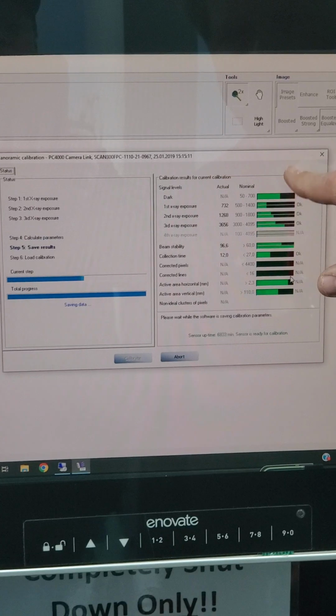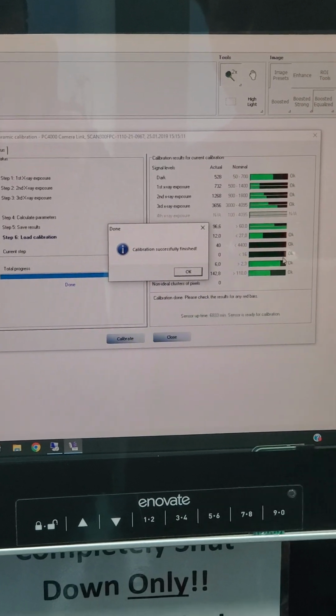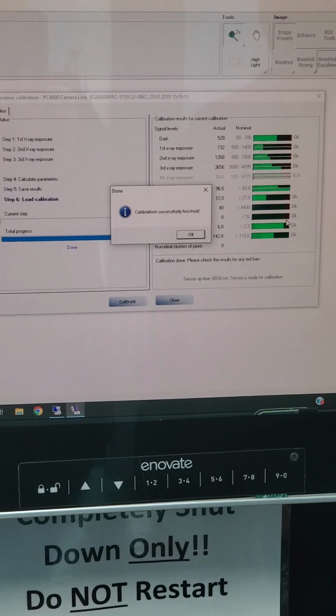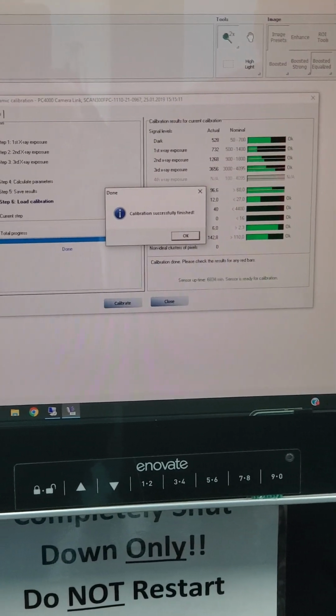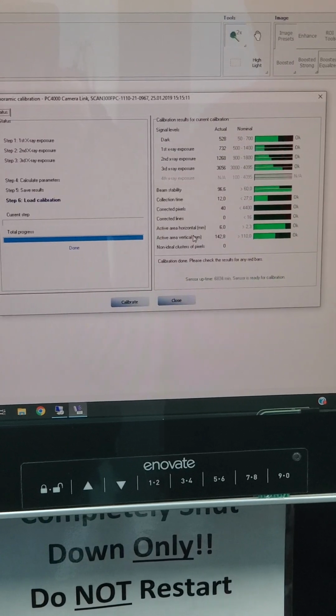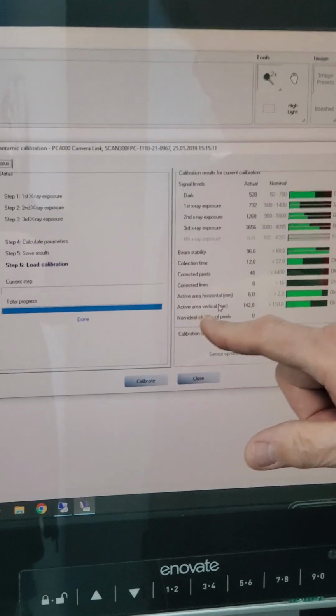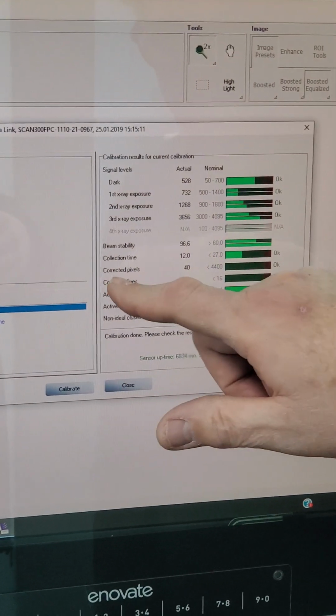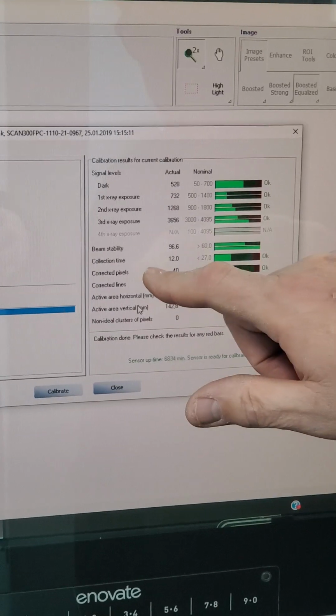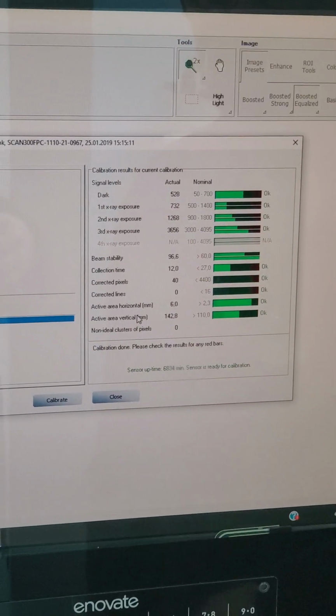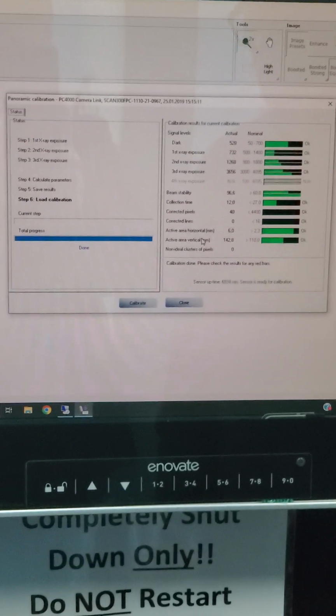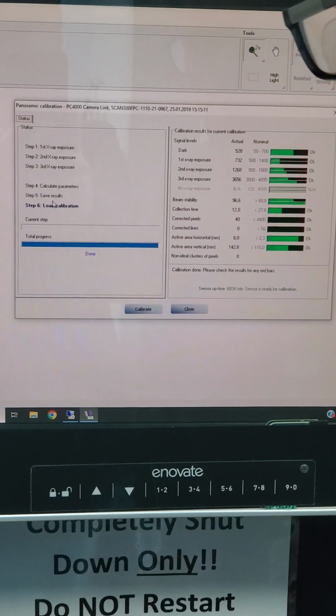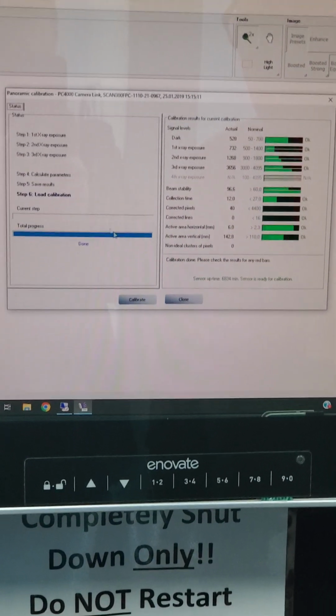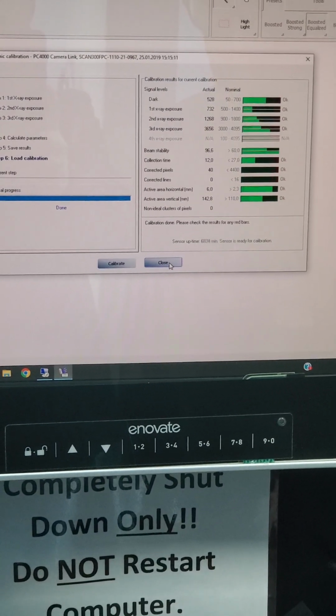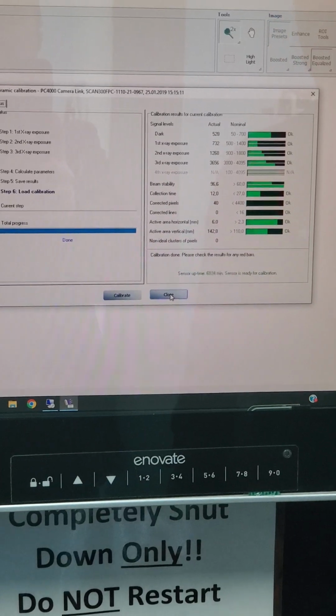So what we're looking for is all of our sliders in the green, and they all are. And we have a successful calibration. Yay! So we're gonna click OK here. We're also going to observe our non-ideal clusters, 0, excellent. Corrected lines, 0, excellent. And only 40 corrected pixels of all of those pixels of that sensor. So the sensor is in A1 condition. It's in great shape. All right, so everything's loaded. Once you do this, it's finished. All you do is close out the calibration. You can take a picture of it and document it if you want to.